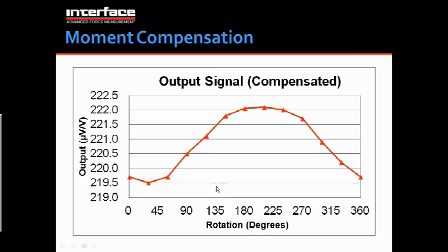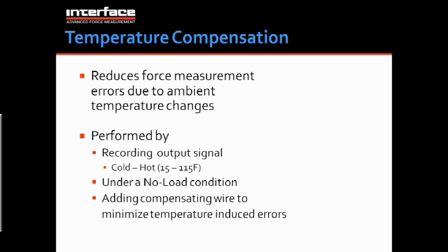So now let's talk a little bit about temperature compensation. And the reason why we perform this on every single load cell that we manufacture is to reduce force measurement errors that are due to ambient temperature changes. And how do we perform it?